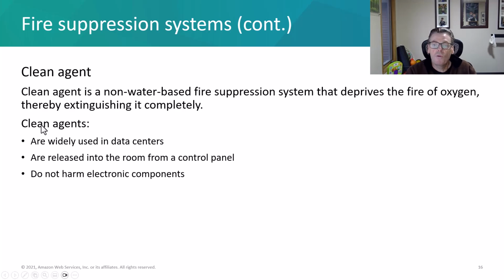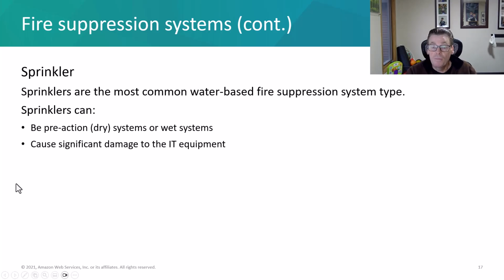Clean agents are non-water based fire suppression designed to starve the fire of oxygen, which will then put it out, because remember that fire has that triad, right? You need a heat source, you need a fuel, and you need oxygen. If we can pull one of those out, the fire will go out. Clean agents are used a lot in data centers. They're released into a room from a control panel, and the nice thing with clean agents is they don't harm the electronic components when they're in use. Therefore, we can salvage the equipment in the event that the system goes off.